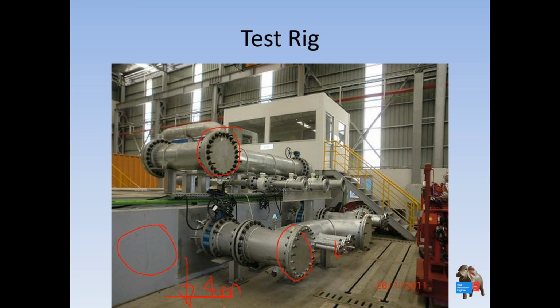From this test rig, as you can see, there is a suction valve here, usually a butterfly valve. And then, for example, you want to test the pump here, and the coupling here, and the motor here, and connect it here, with water in, and the discharge you put back into here, and circulate it in a closed loop.